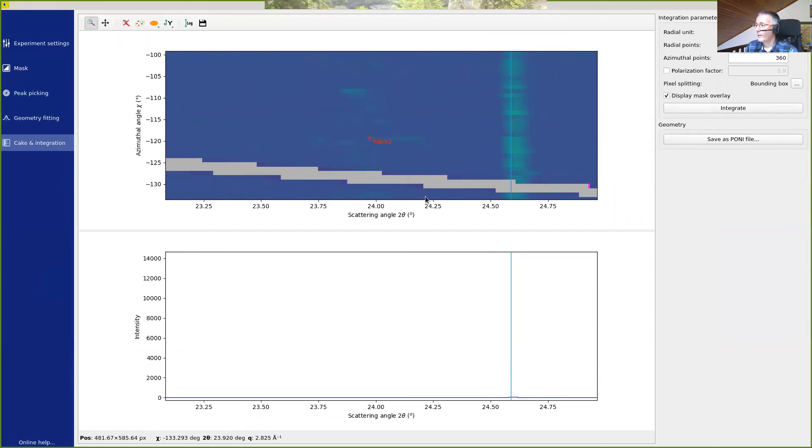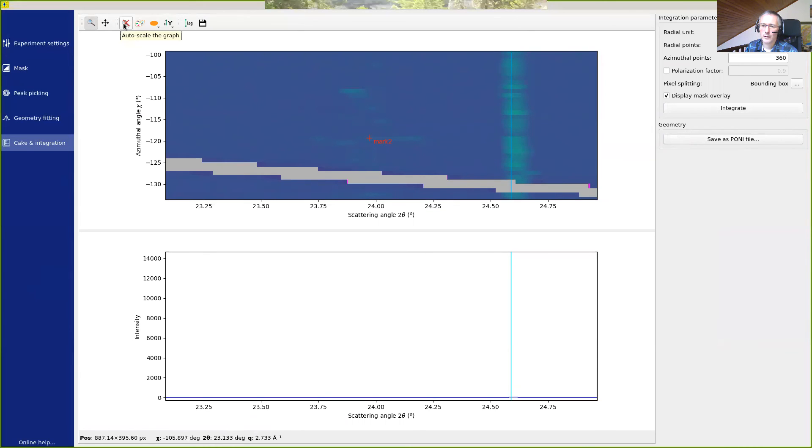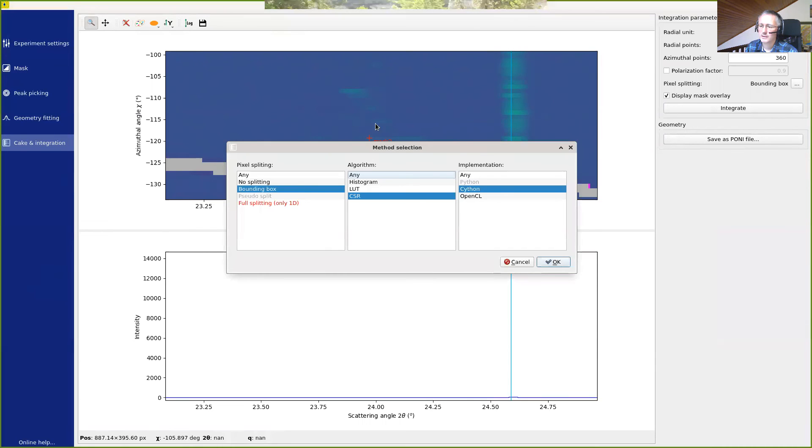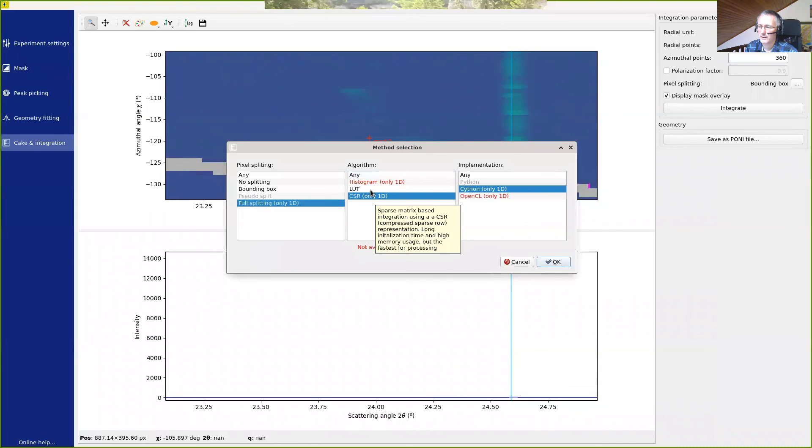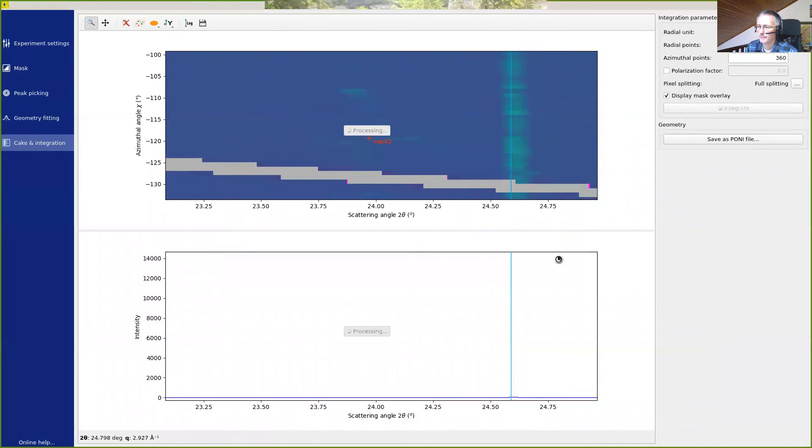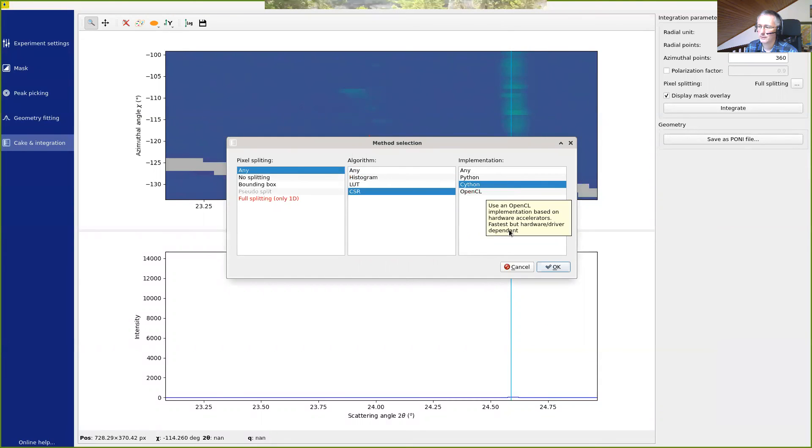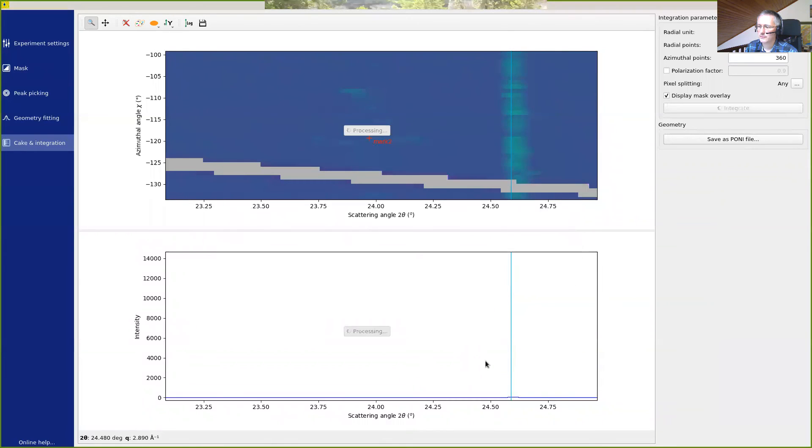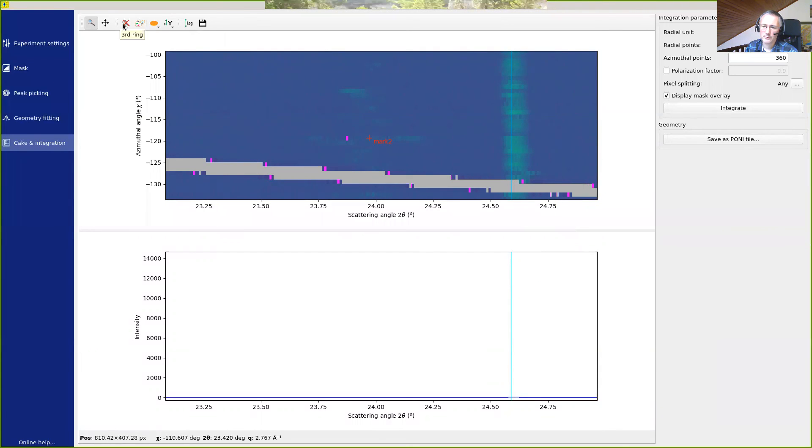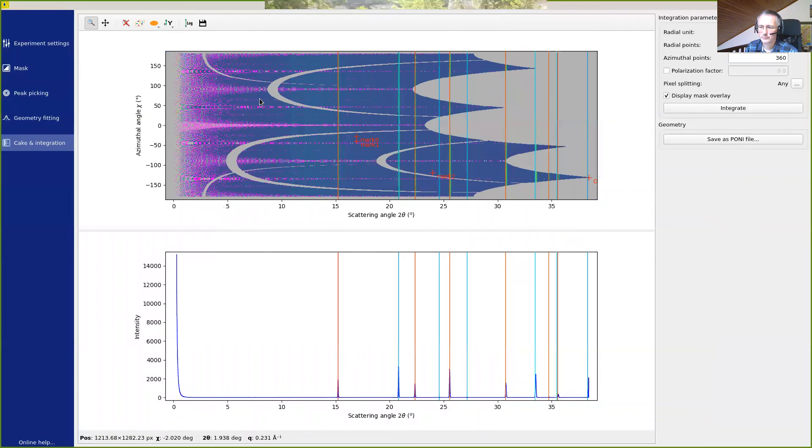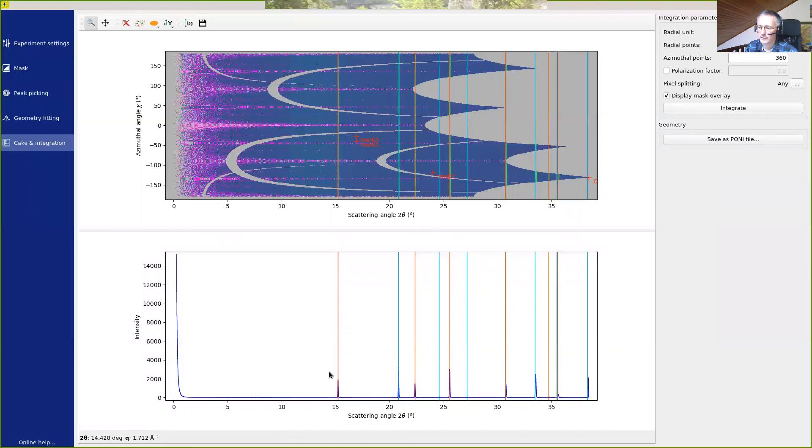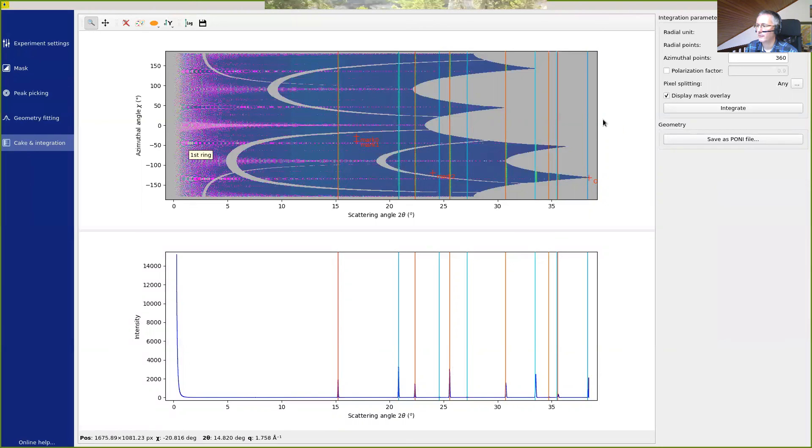Okay with this I'd like to show you one last thing. You can tune also the pixel splitting scheme. For example, you can select a more precise splitting scheme which should give you slightly sharper peaks, but the sharpest peaks are obtained without any pixel splitting. You see that the peaks are very sharp. The drawback of this method is that when we zoom out we see a moiré pattern here which is clearly visible and most people don't want to see it. If you want precise peak position you have to suffer this moiré pattern, but the great thing is that you can tune and select if you want to use the pixel splitting or not.